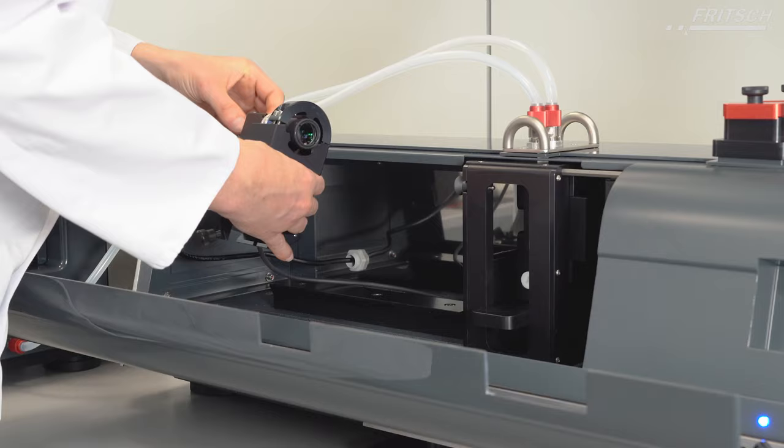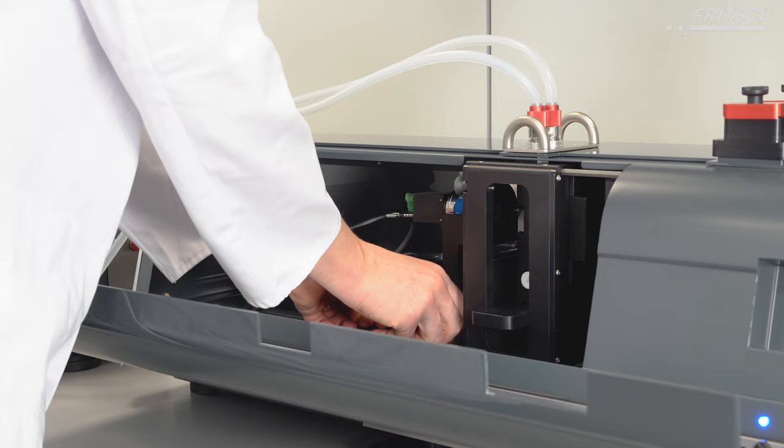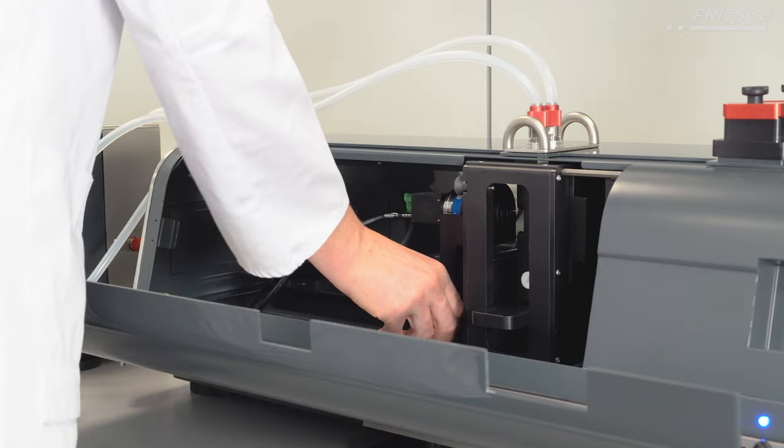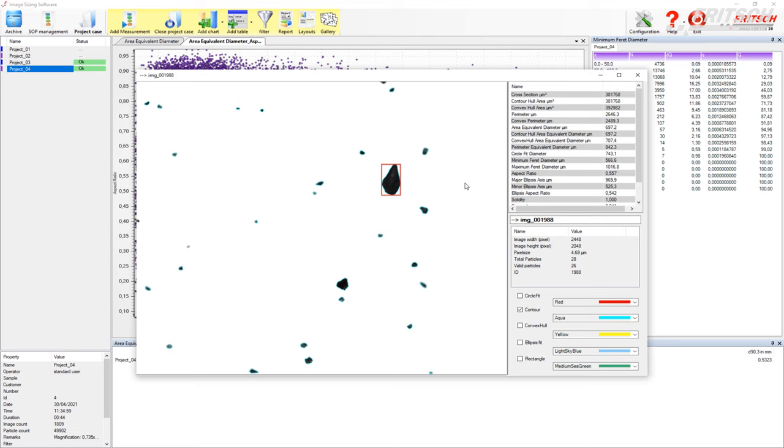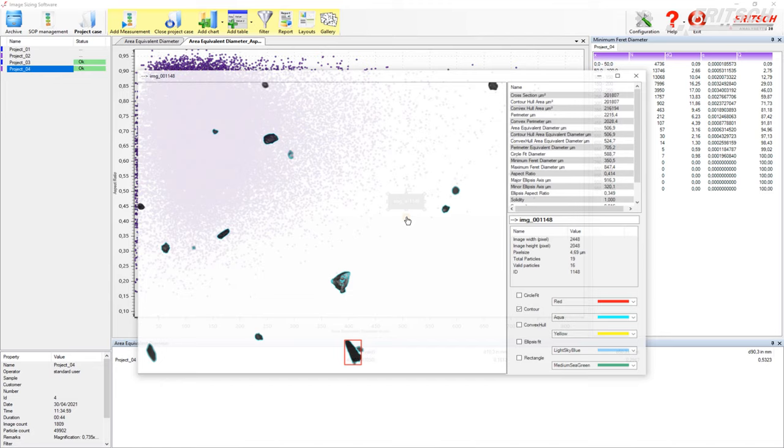With only one high-performance industrial camera, the ANALYSETTE 28 image sizer covers an extremely wide measuring range and ensures highest resolution of even the smallest particles with a rate of 75 frames per second. In one image, large and small particles can be directly captured, displayed, edited, and deleted.